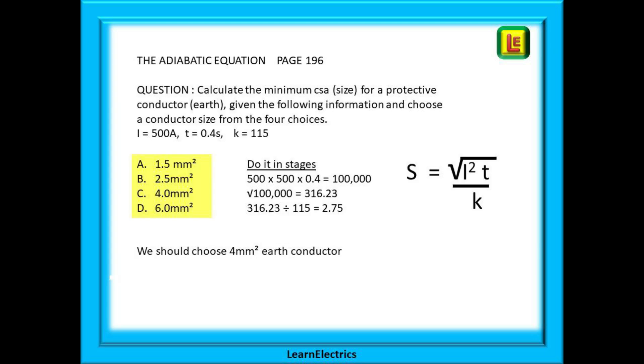Let's have a look at a typical exam question on the adiabatic equation. Calculate the minimum cross sectional area or size for a protective conductor, the earth, given the following information and choose a conductor size from the four choices. The data provided is i equals 500 amps, t equals 0.4 seconds and k equals 115.